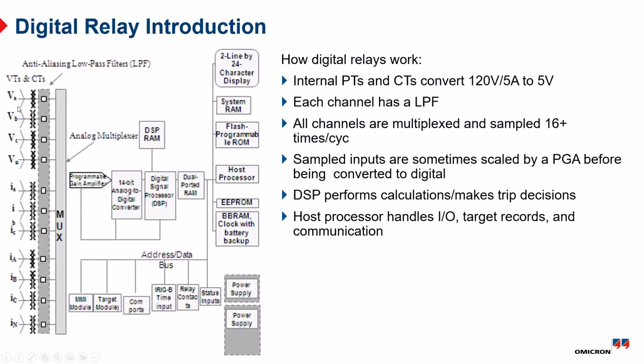On the left here, you can see we have the voltage and current input. So from the system, we have, depending on where you live, 1 amp or 5 amp nominal CT secondaries. They come into the back of the relay at 1 amp or 5 amp, and then it gets stepped down inside. Usually on the bottom of the relay, you'll see there's a bunch of CTs and PTs, and they get stepped down to like the millivolt level. And then there's a low pass filter. Low pass filter basically clips off all the harmonics above a certain point to prevent aliasing. I'm not going to get into that here, but in any case, it helps the relay properly measure voltages and currents.